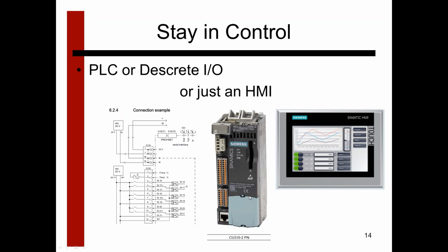There was a thrust involved on the pullout, so that's really what it was designed around, but that's all he wanted. Push a button, it goes forward. Push a button, it goes backwards. He doesn't need a PLC for that. And drives have pre-configured and stored indexes built into them if we select the right drive based on your application. You can see a simple wiring diagram on the left. And that's something else that CNE Sales helps with, is recommended ways on how to wire your drive if you're using discrete inputs, for example.